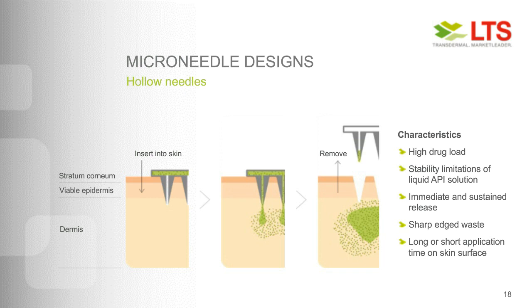And if everything is released, you pull it out, and this facilitates a high drug load, which is possible because the portion of the reservoir can be very large, actually. But you have, of course, the same problems with a liquid reservoir as with all injections. You can do immediate and sustained release. Nevertheless, you have sharp-edged waste again, because these hollow needles are made from metal most of the time. And depending on whether you have a sustained or immediate release, you have a shorter application time on the skin surface. So you are quite flexible.